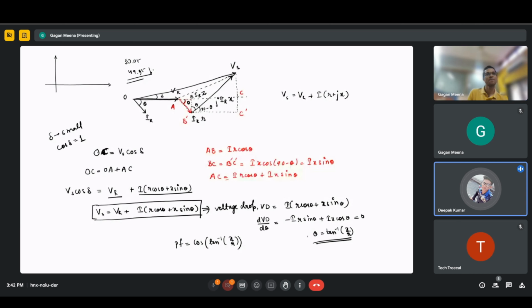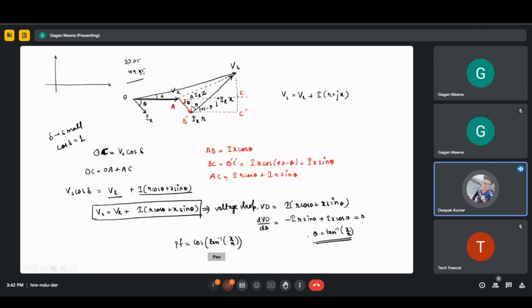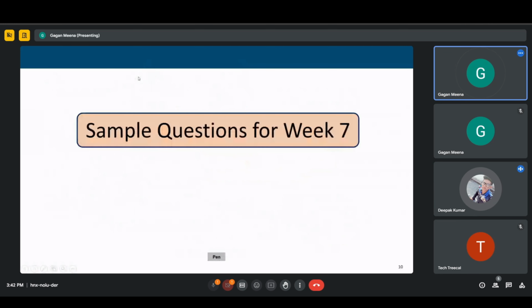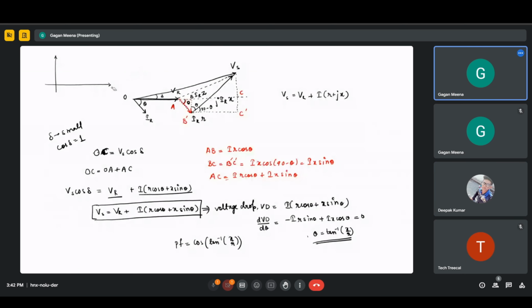Sir, whenever the real power changes, we have to change the steam input of the turbine, and for reactive power, we have to change the excitation. Yes, correct. So excitation control is there, and valves are also controlled. When demand increases or reduces, the valve setting is changed, so the valve controls the steam input to the turbine. All these things happen automatically.